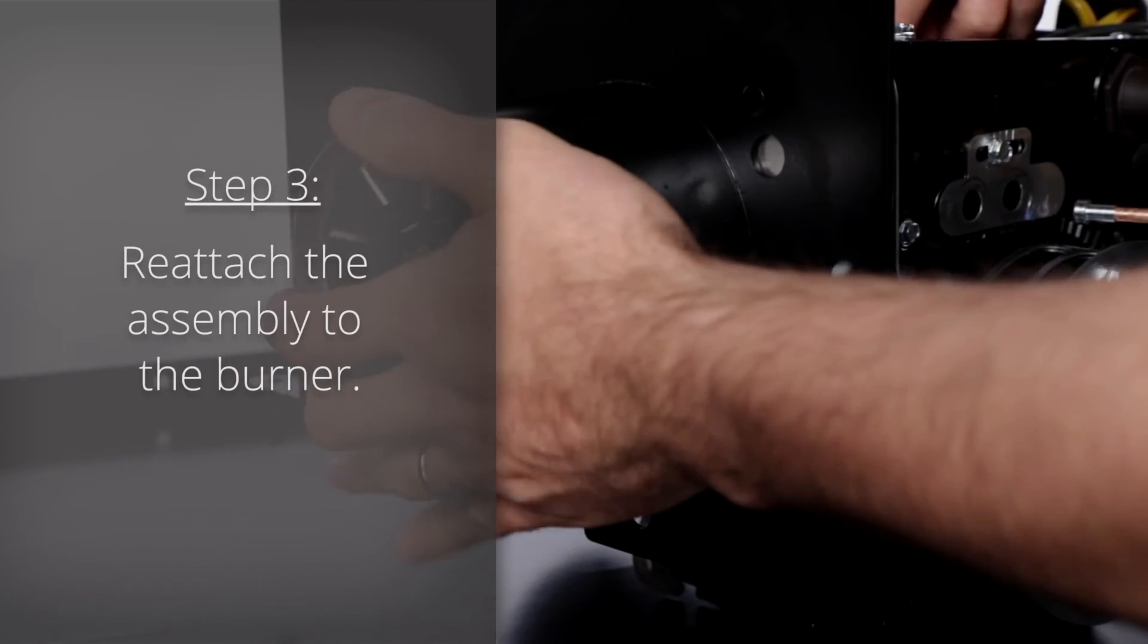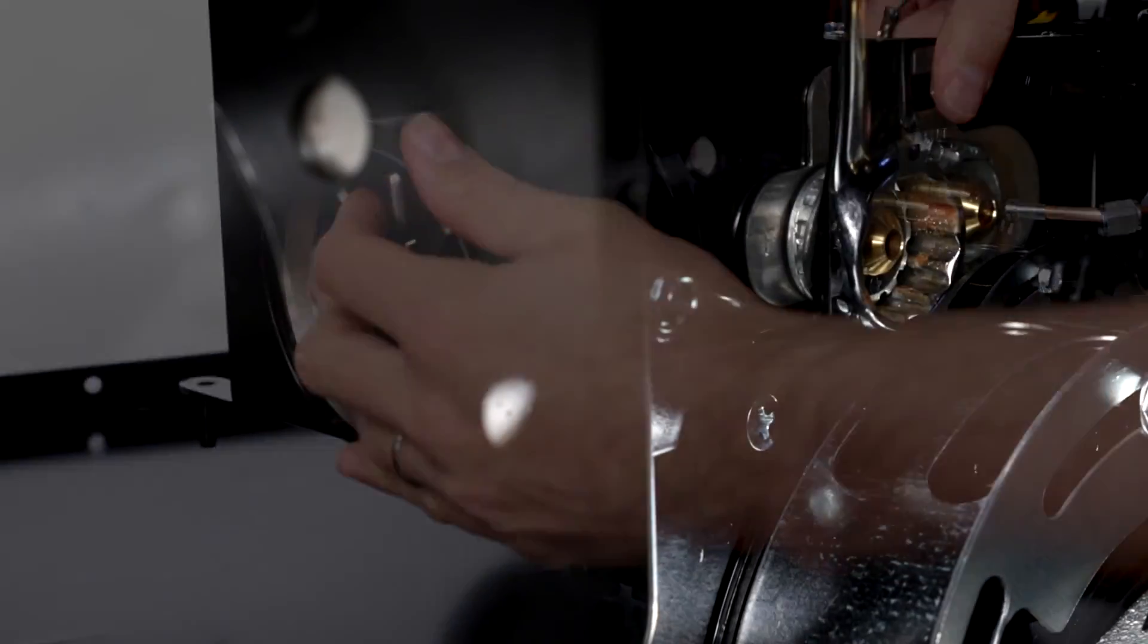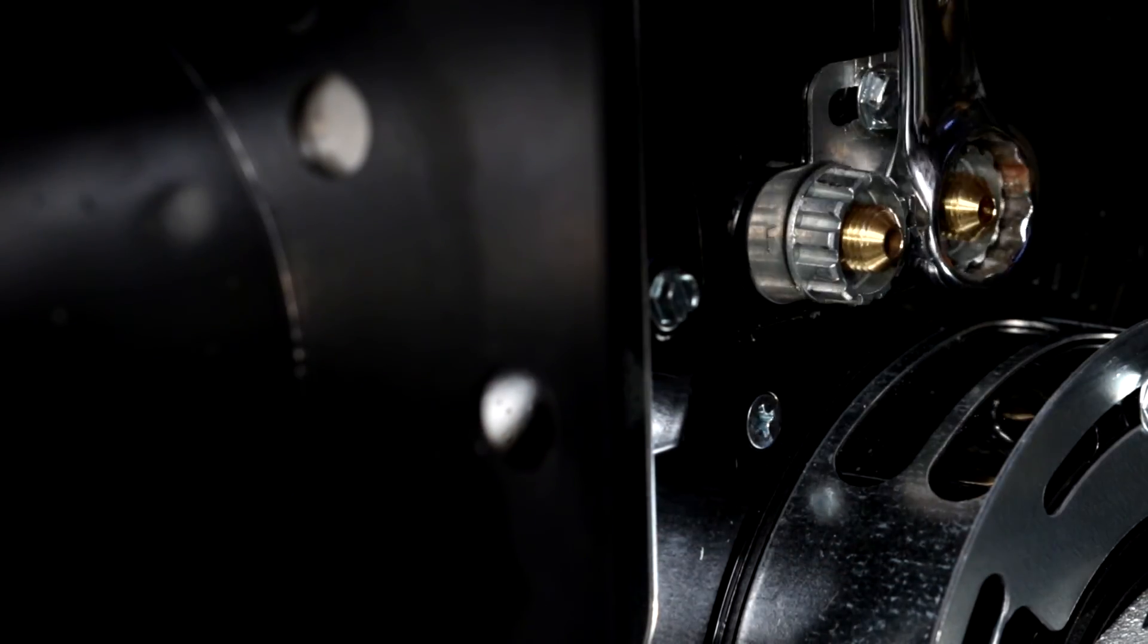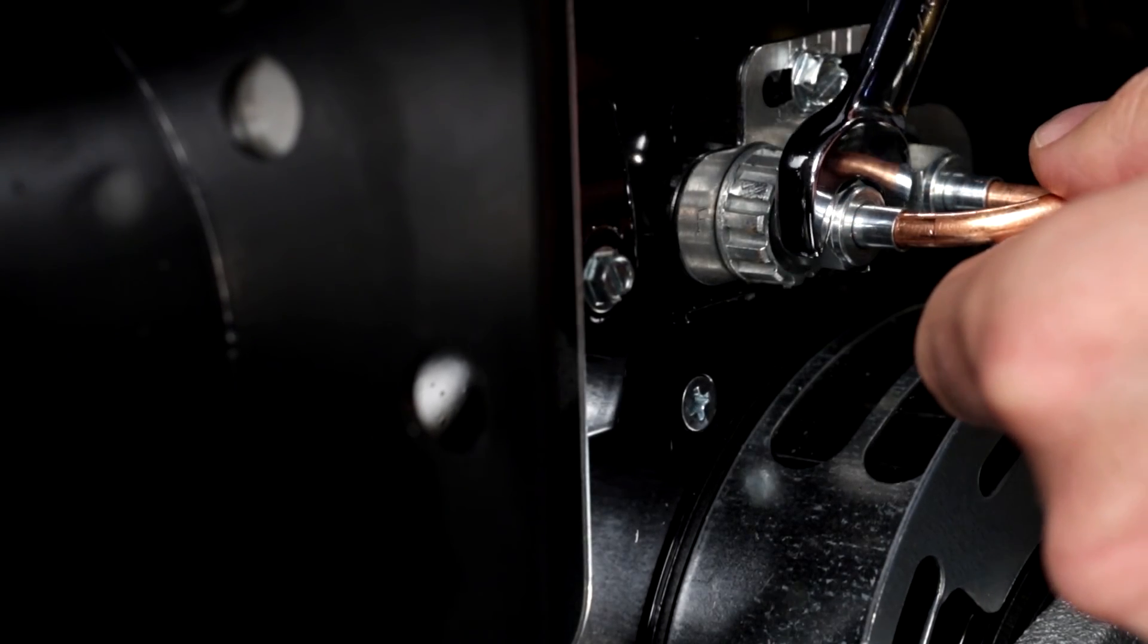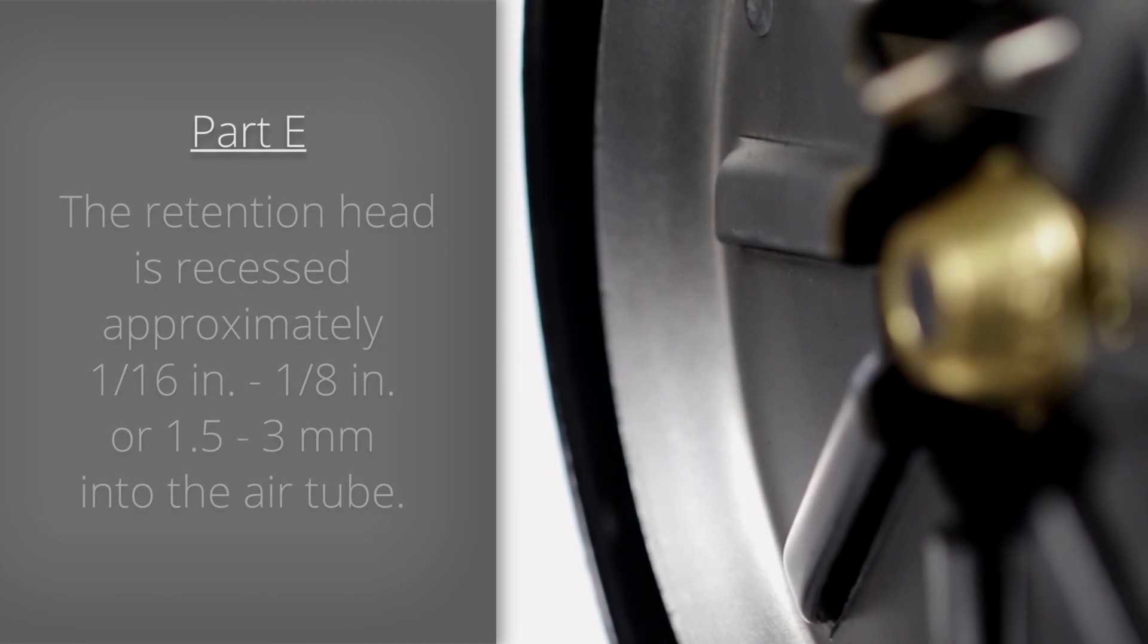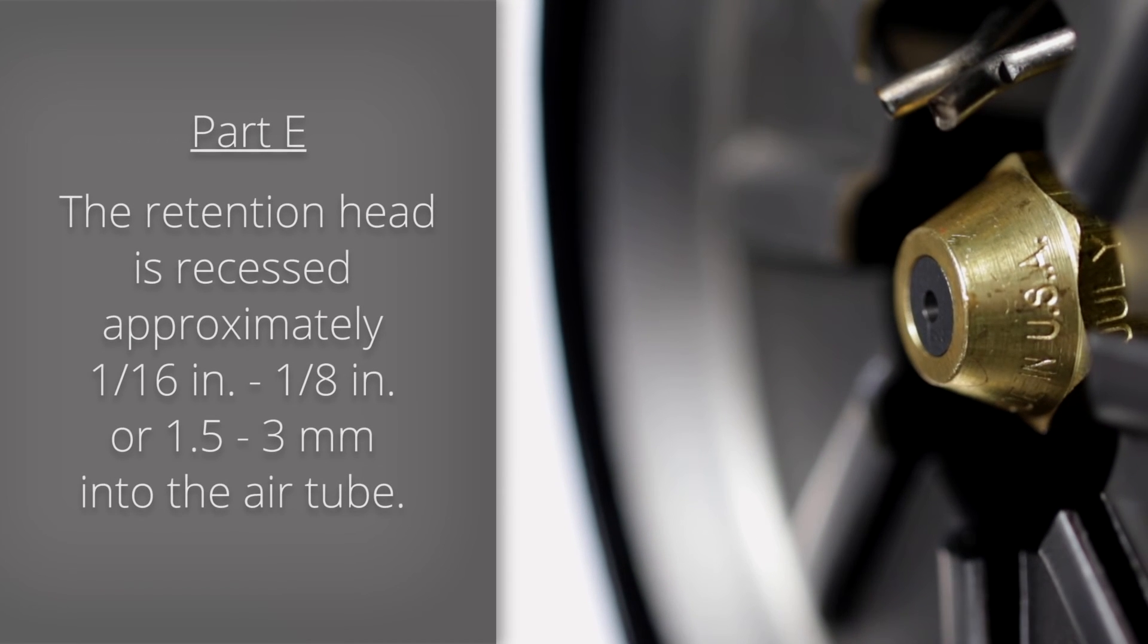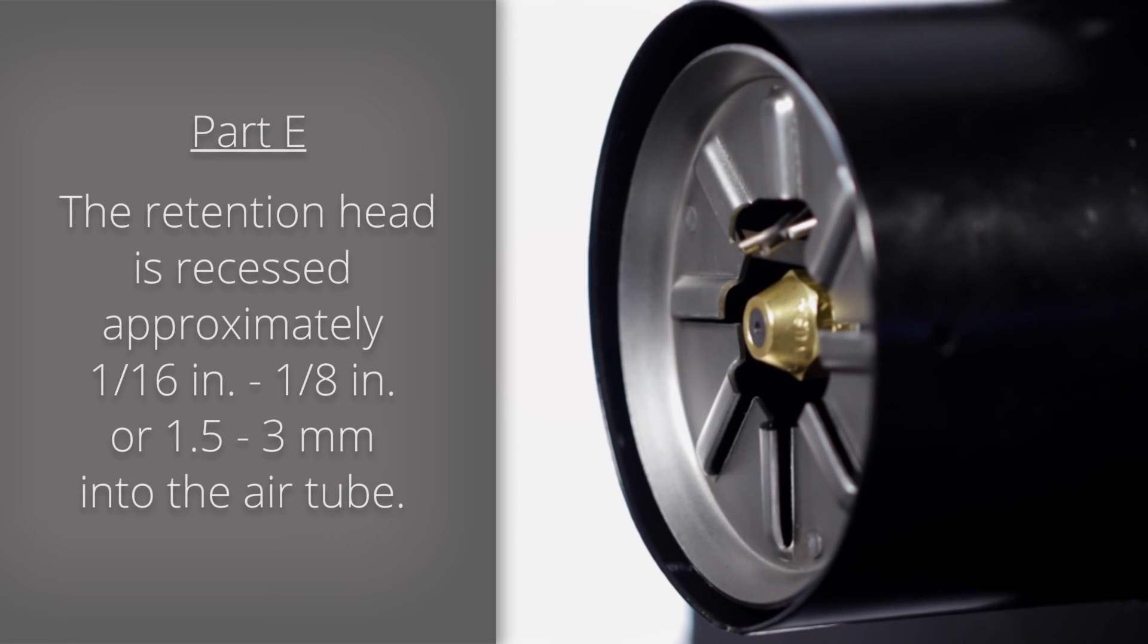Step 3: Reattach the assembly to the burner. Part E: The retention head is recessed approximately 1/16th to 1/8th of an inch or 1.5 to 3 mm into the air tube.